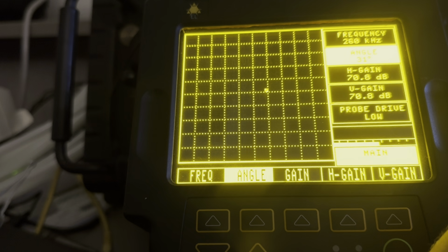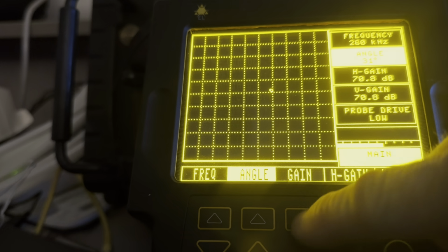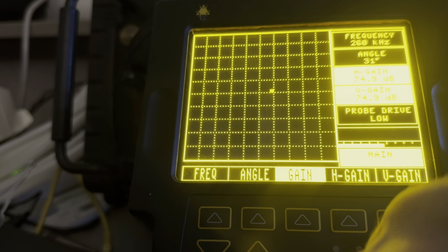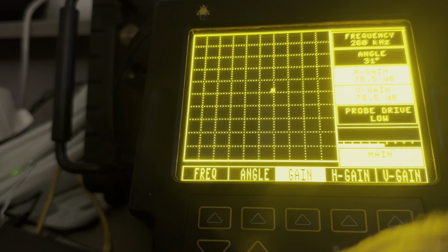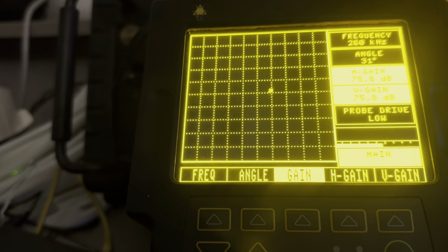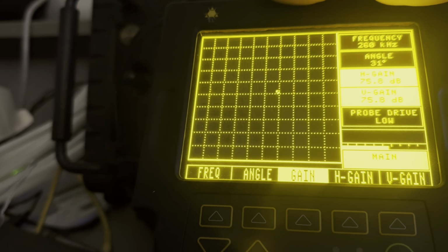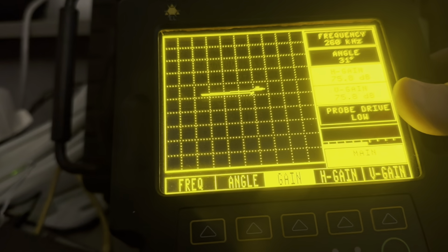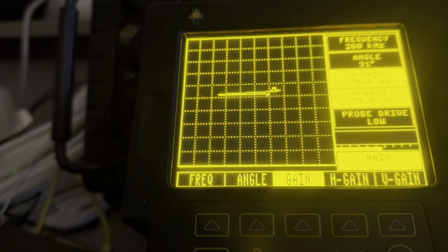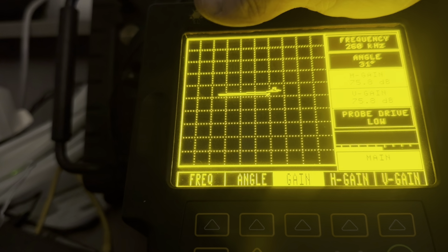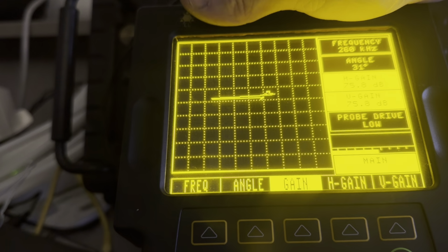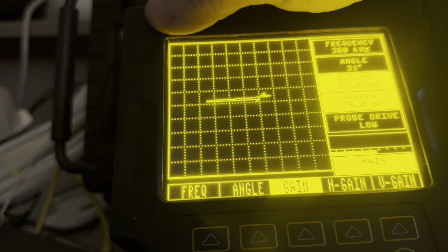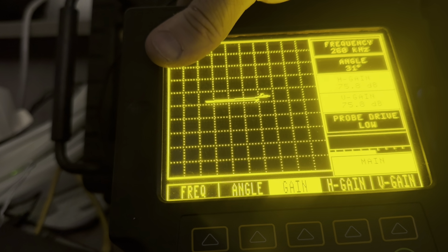So I've tried changing my drive voltage. I could try taking my gain up a tad. That's not going to do anything because this probe seems to be dead. However, remember that selector on the top of our adapter that says B and R? Well, the R is for driver pickup, or more specifically, reflection mode. So now I got on reflection mode, but I still have this other selector switch in the back. And where is it? Right here.